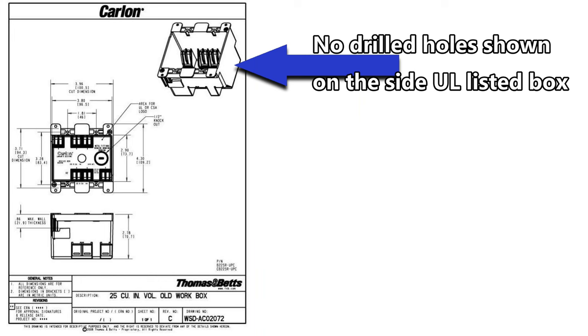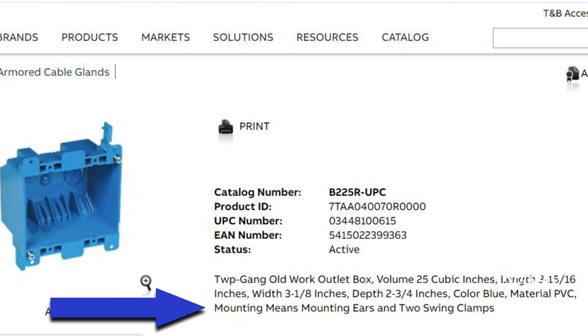This particular box is UL listed. And then when we go to the Carlon website and you look up the drawing, the UL listed drawing, we find that there are no drilled holes in the side of this non-metallic box. And then under specifications for this box, right where that blue arrow is, it says mounting means mounting ears and two swing clamps and that's all it says.